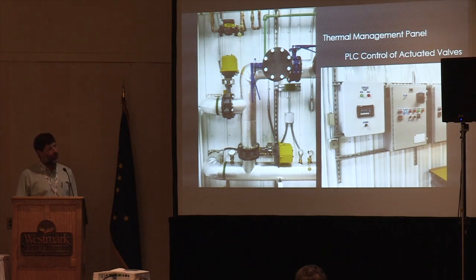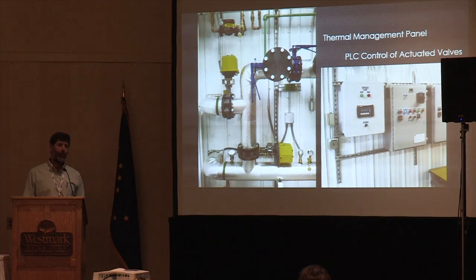So when you put in a heat recovery system, it's nice to have actuated valves that are actually controlled by a PLC or a thermal management panel that can more closely regulate the temperature in the heat loop. One thing we don't want to do is overcool our engines, because they become less efficient. So we have to be careful about how much heat we send to the radiators and how much heat we send to heat recovery.